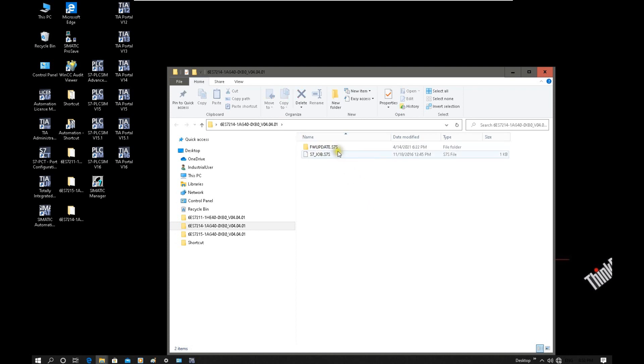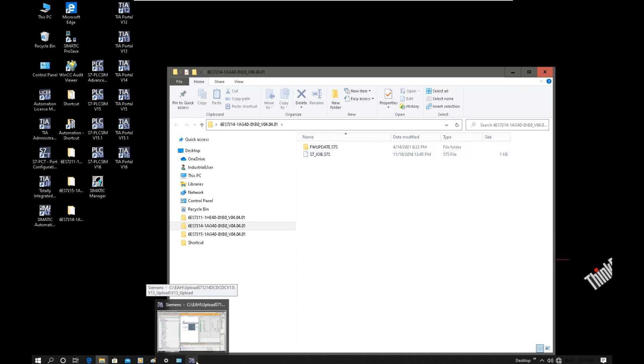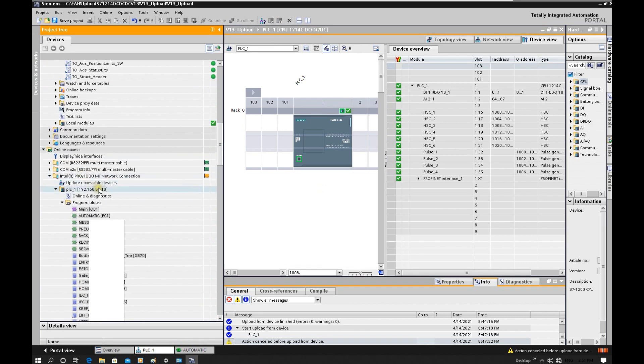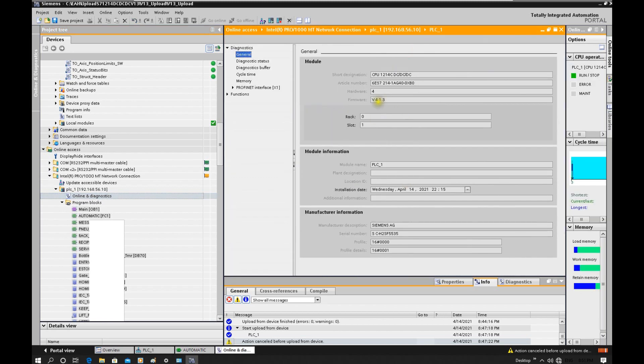How can we upgrade this firmware? We need TIA Portal. Come back and use online access. To upgrade this CPU we do not need to create a project — we can directly shift to the project view, select online access, and click online and diagnostics. Once you get this page it shows the current firmware and the CPU type. Make sure the firmware file you downloaded matches this article number.